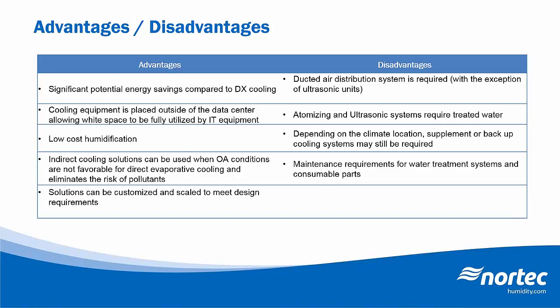By centralizing the cooling equipment outside of the data center, the white space itself can be maximized to be fully utilized by the IT equipment. Another advantage here is that in areas where the outside air dew point is outside of the acceptable range and we may need supplemental humidification, adiabatic systems can provide very, very low cost humidification compared to the cost of, say, traditional steam humidification.